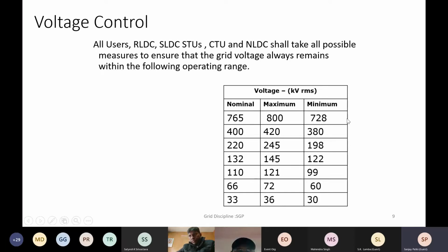These are, again, provisions from the grid code that all users and the load dispatch center shall take all possible measures to ensure that the grid voltage always remains within the following operating range. So there is a nominal voltage, a maximum permissible voltage, and a minimum permissible voltage. And there is a set of actions at different levels. There is a role to be played by generating companies, transmission companies and the distribution companies to ensure that voltage remains within this band. And we'll see what those various actions are.